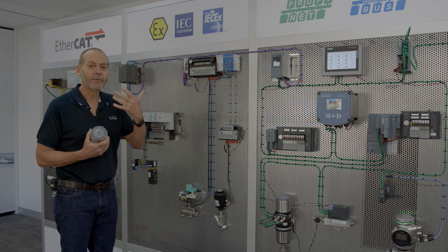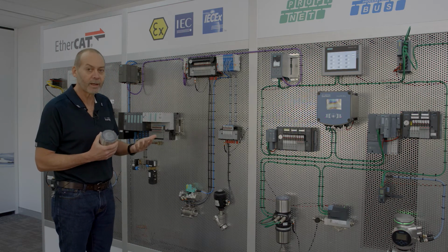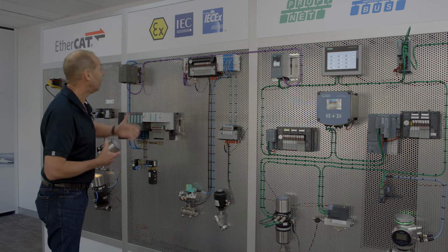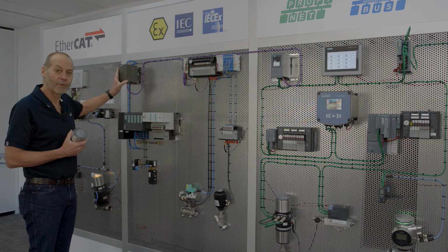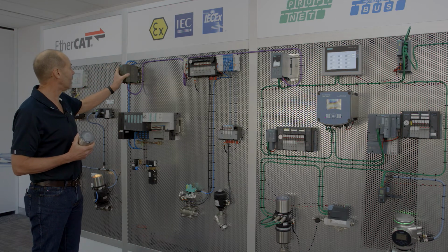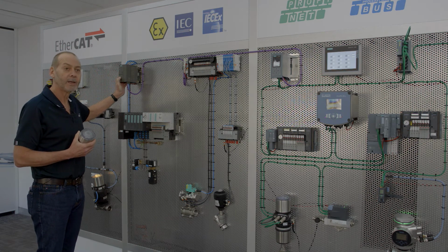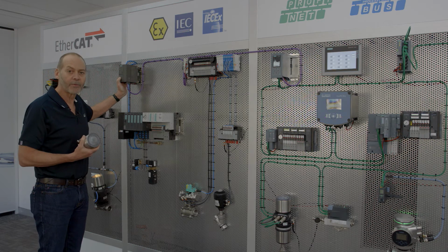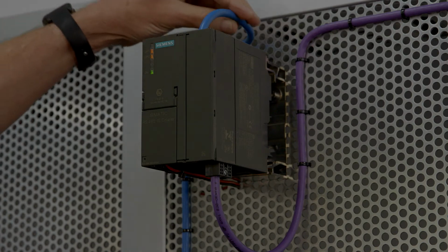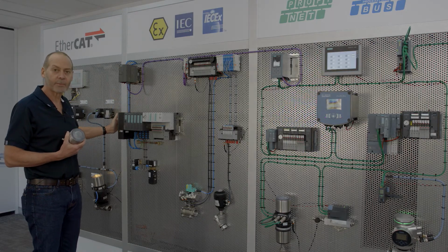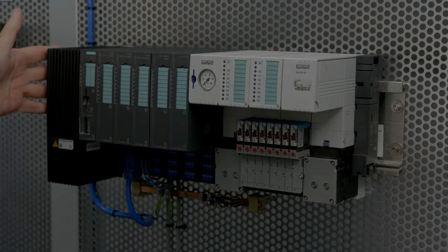If you then have the need to mount all of your devices directly in the Class 1 Zone 1 area, we have another solution for you as well. We've continued this on the Profibus network, and this one is specific to Profibus. Here we take the Profibus and put it through an RS-485 intrinsically safe coupler. Consider this as a barrier for the Profibus RS-485. We go in with a standard Profibus and come out with an intrinsically safe Profibus that can run directly to Class 1 Zone 1 in the field.